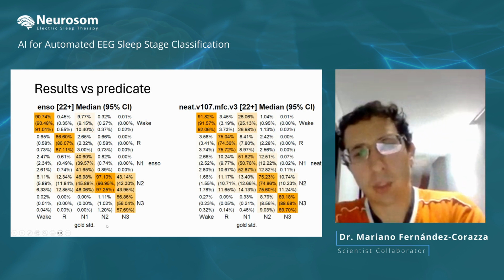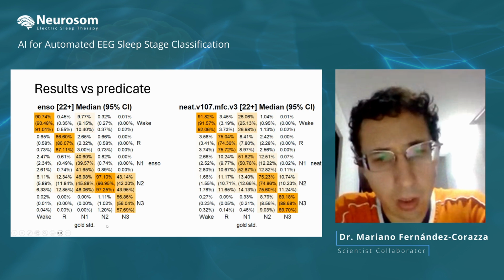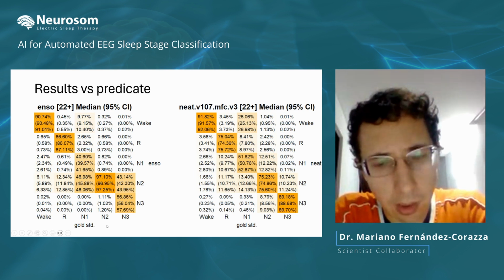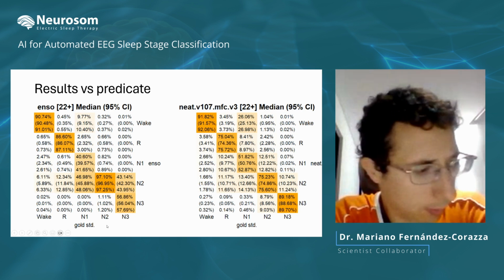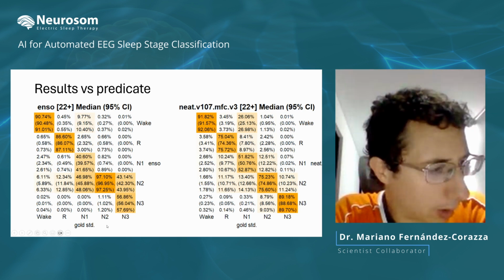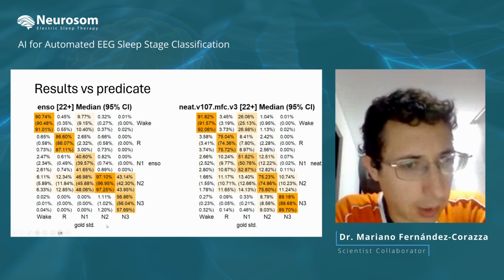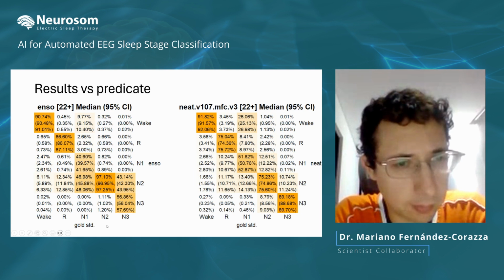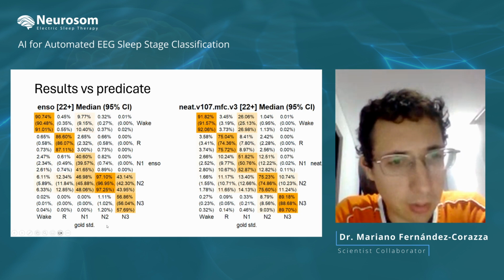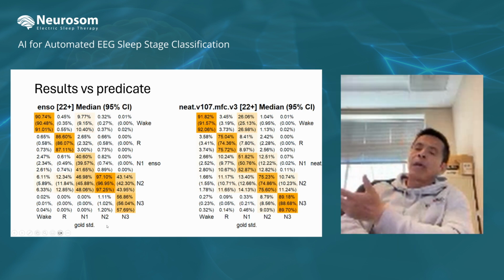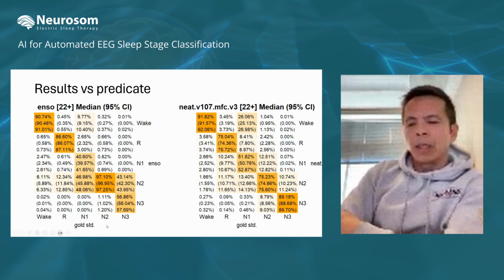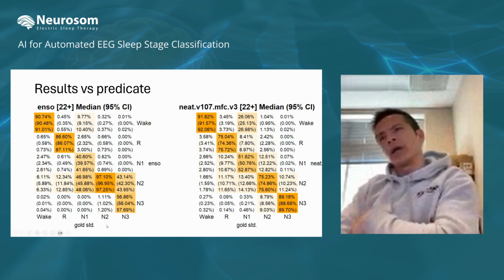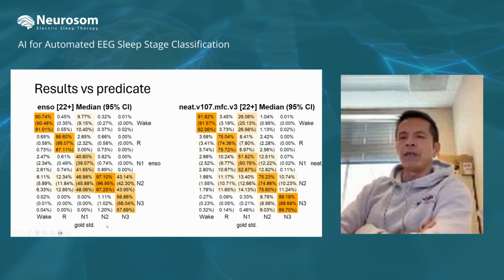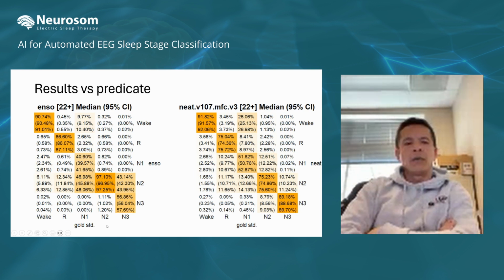No, I think that for the validation, what they only ask is a comparison against the predicate. So they're assuming that device is successful and it works well, and so we have to use that as our standard. Yeah, so that's the 510K framework. That's right. That's what we discussed during our pre-submission, and the feedback that we got was that it was the predicate.